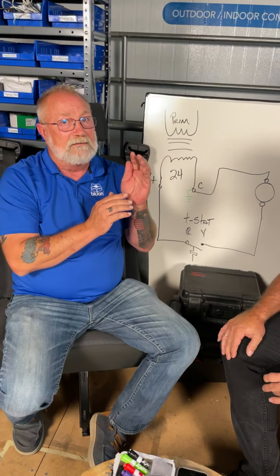So one of the things you can do, and I've run into this a couple times this week, they've got 24 volts to the contactor coil. If you read the contactor coil from here to here, and you're going directly to the contactor coil, and you have 24 volts here, you got a bad contactor coil. Plain and simple. But what happens a lot of times is here's these wires out here where it connects into the unit, and they want to read the wires here, and they say, but I got 24 volts going into the contactor coil. Where you really don't have 24 volts going into the contactor coil, you have 24 volts going into the condensing unit. You can have 24 here and still not have 24 at the contactor coil.